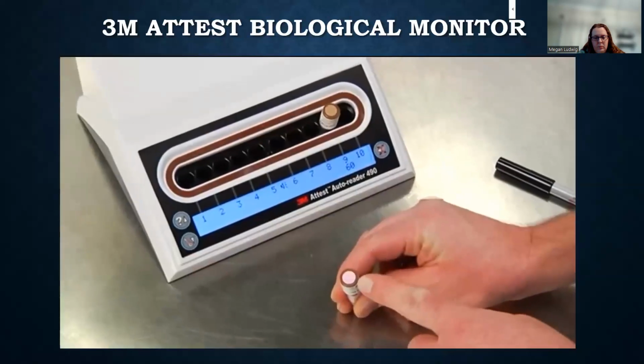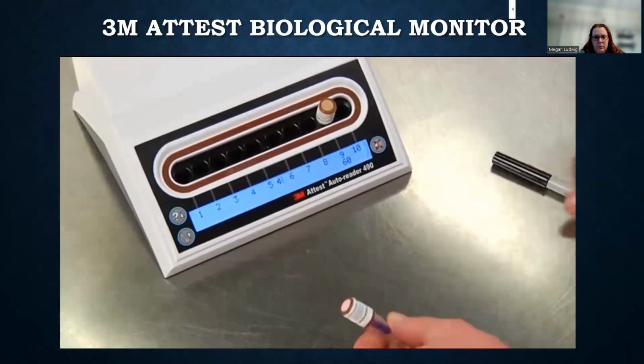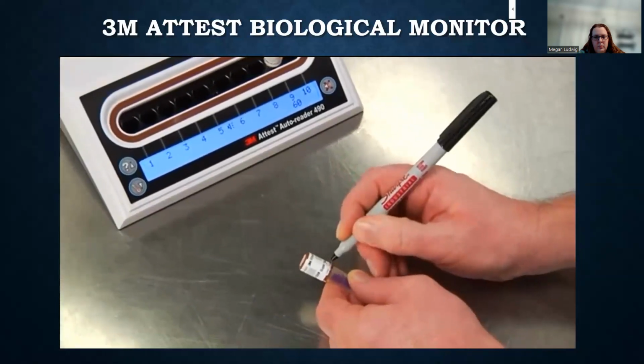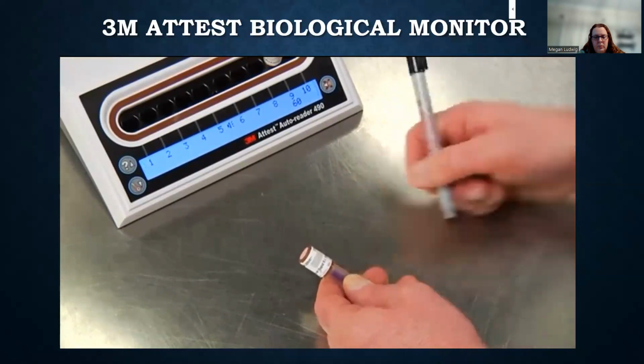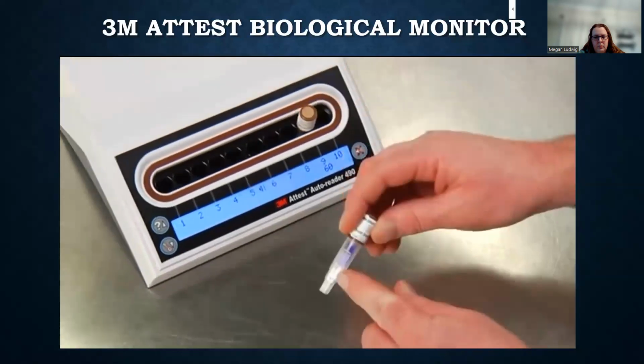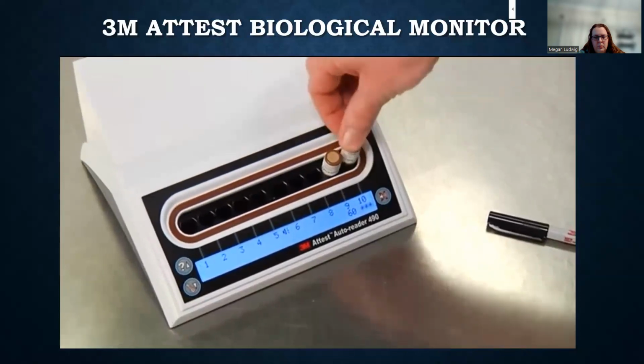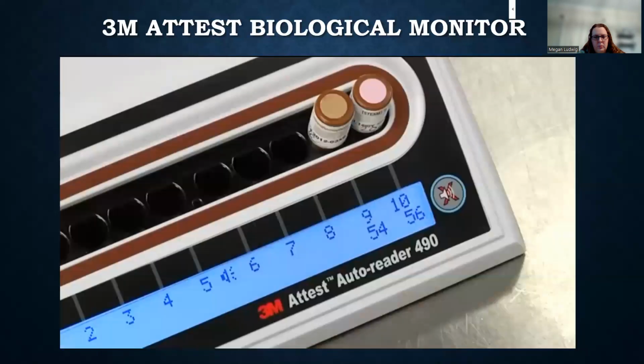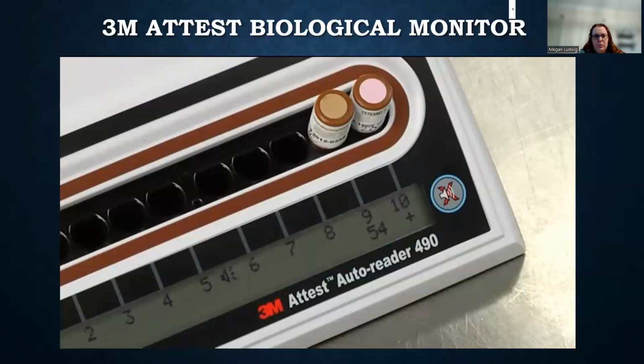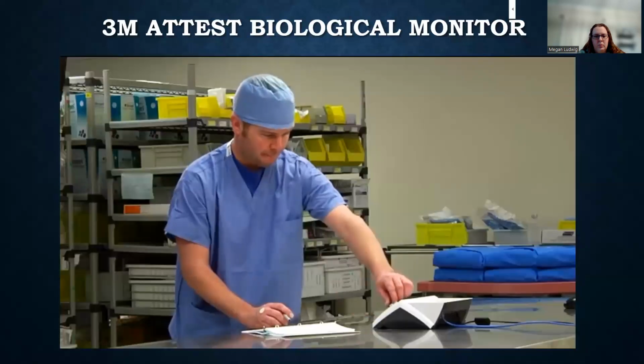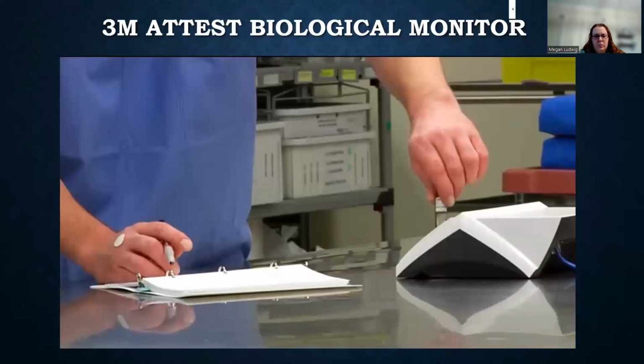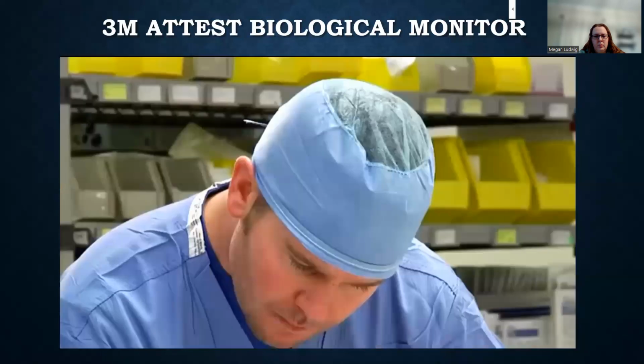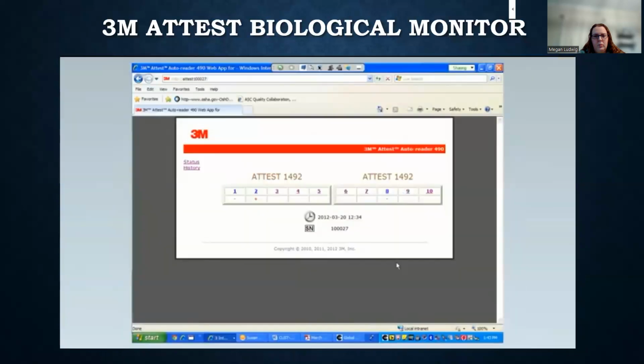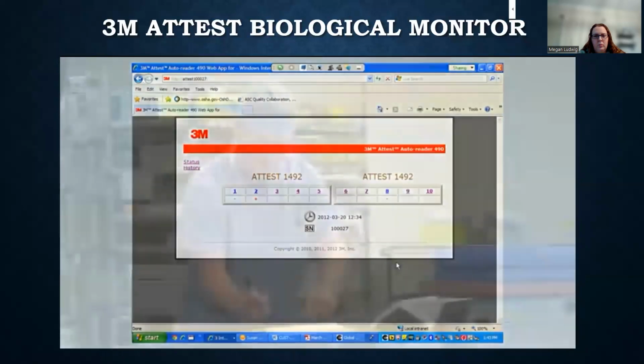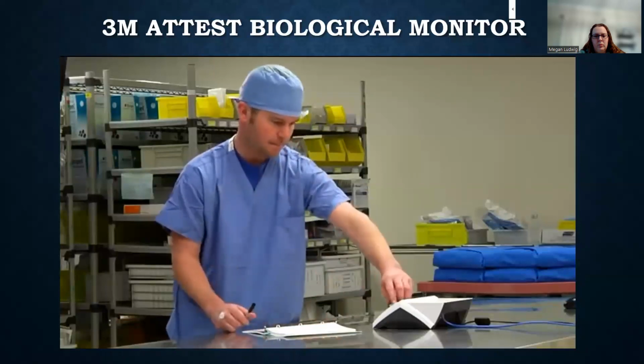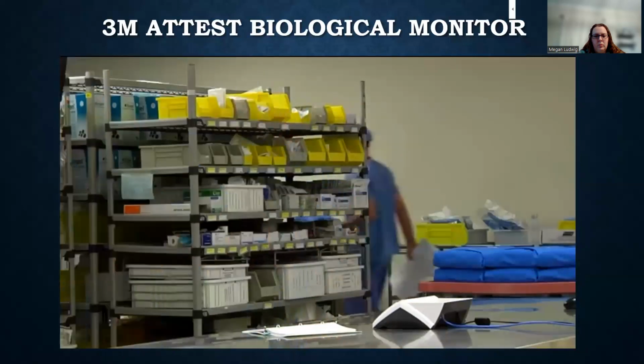Each day that a processed 1492 VBI is incubated, activate and incubate an unprocessed 1492 VBI as a positive control. The positive control should be from the same lot code as the processed biological indicator. The positive control BI should provide a positive fluorescent result. After a BI test is complete, the next step is to record your results. You can use traditional record-keeping methods or the 3M Attest Auto-reader 490 web app. The 1492 VBI is normally discarded after the fluorescent result has been recorded.